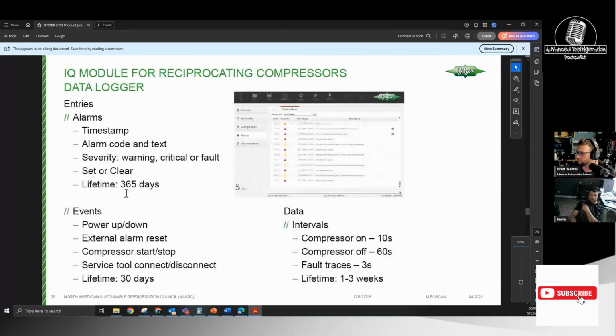Yeah. I might have to make one, but right here you have your faults and your lifespan counters. So to reset the faults, I was just power cycling it. I had it wired all jacked up when I was doing it, because the way I had the high pressure switch wired and how I thought it had to get wired, it kept throwing a fault. So for the high pressure switch being open, it turned out that the skids were wired with the low pressure switches switched from compressor to compressor. But that's good. That's really good. That's all right.